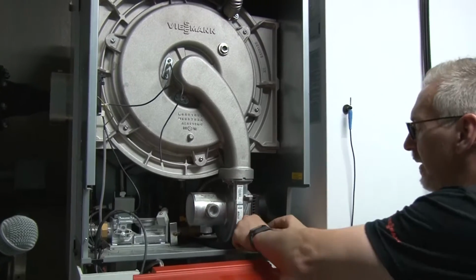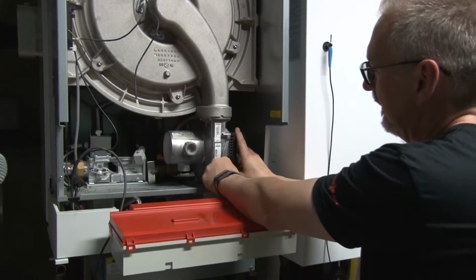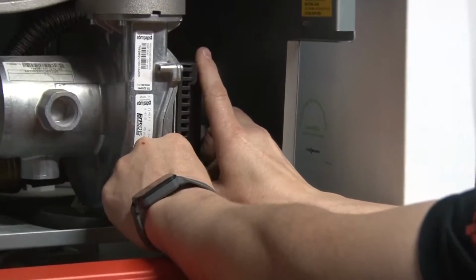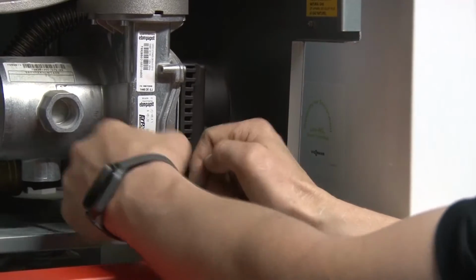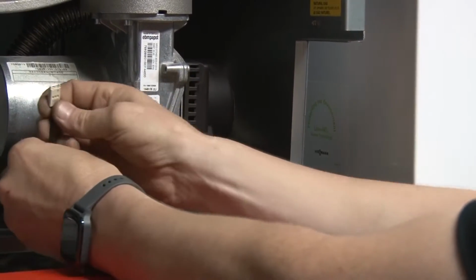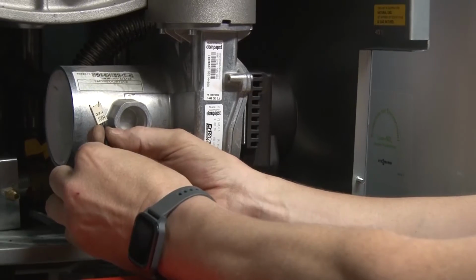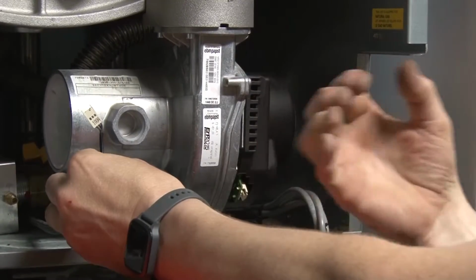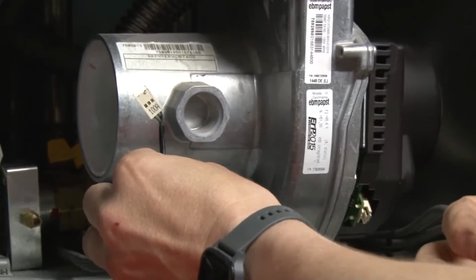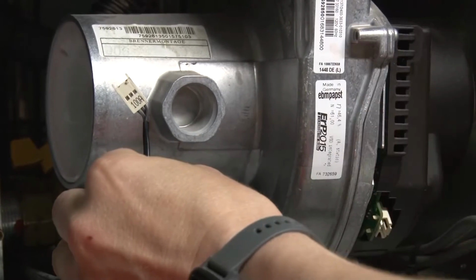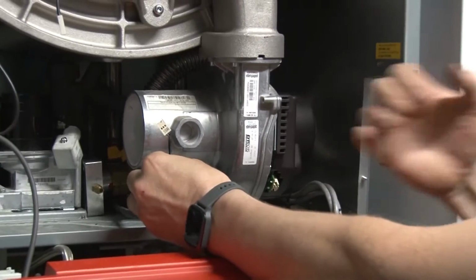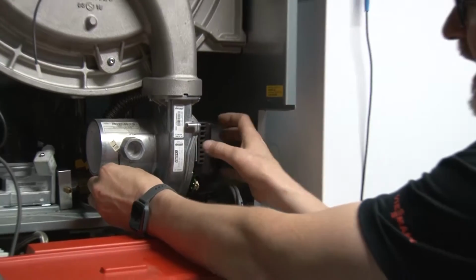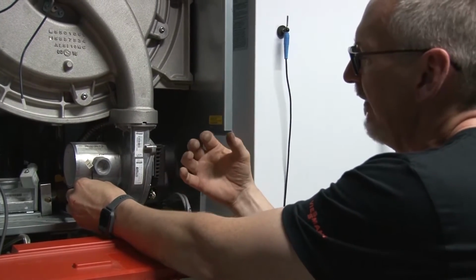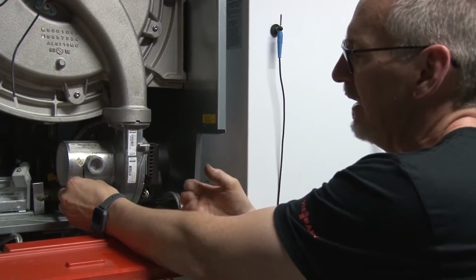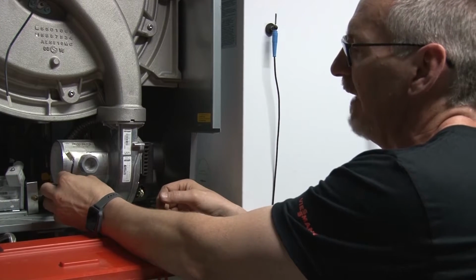We've got a couple of plugs here on the burner fan. So modulation of your boiler is always about fan speed, and that's what this little plug is here, the 100A. It basically is the signal from your control. When the burner wants to ramp up modulation, it's going to pulse a signal, and you're going to get a faster pulse of electricity, or cycle I should say, to your fan, and that's going to increase the fan speed. So it's a modulating fan based on load.